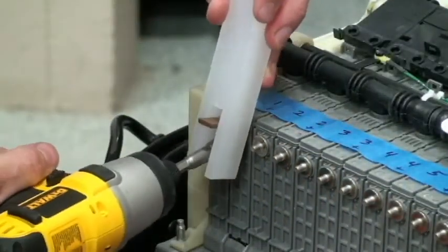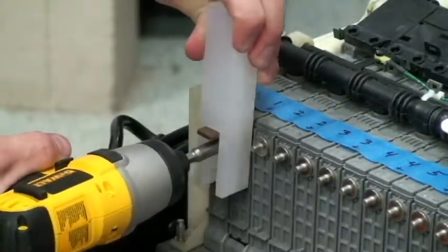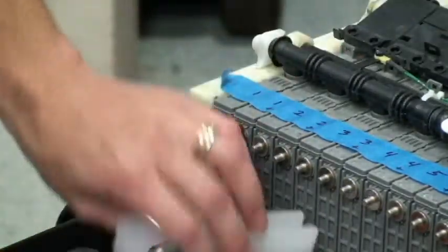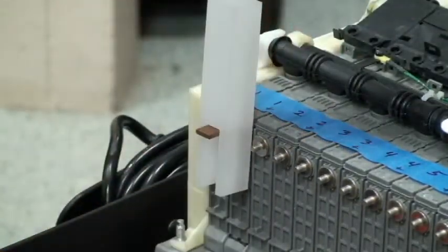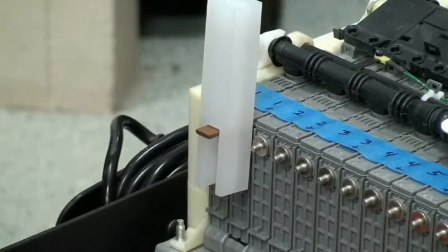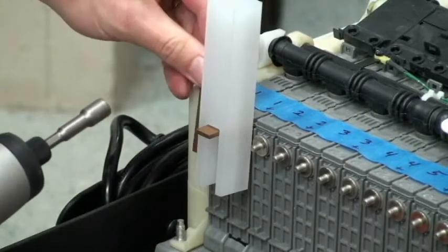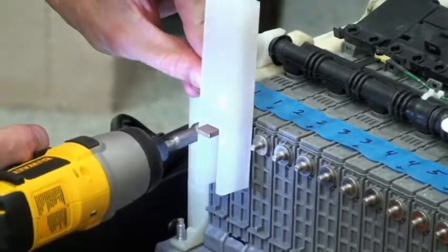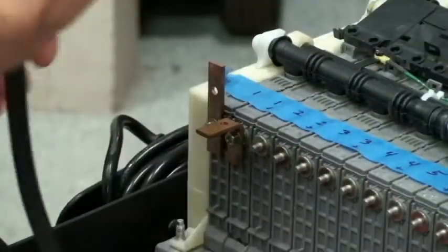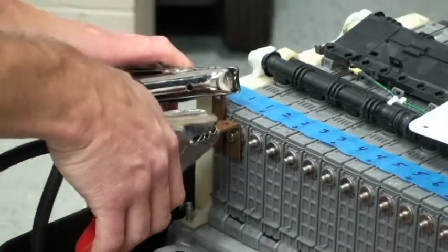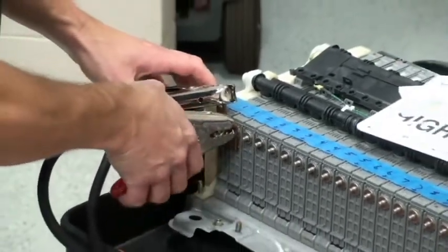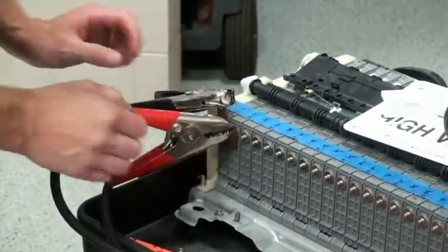The next step will be to install the bus bars. Notice the use of the white isolator bar. The white isolator bar will ensure that there is no arcing between the two bus bars when they're being installed or removed. Once the bus bars are installed, the power test plus and minus clamps can be installed on the plus and minus battery modules.